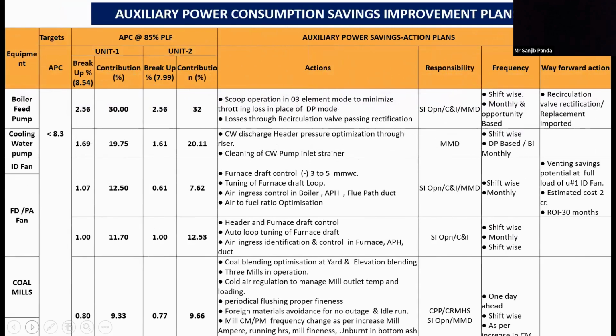Similarly, for auxiliary power consumption reduction, we have focused on individual equipments, the equipments which are taking a higher power consumption, like boiler feed pump, cooling water pump, ID fan, FD fan, PA fan, coal mills. And in each of these, we have chalked out several action plans on how to actually optimize the power consumption and ensure that overall auxiliary consumption is reduced. And we have achieved that, as we have seen during implementation. Next, ma'am.